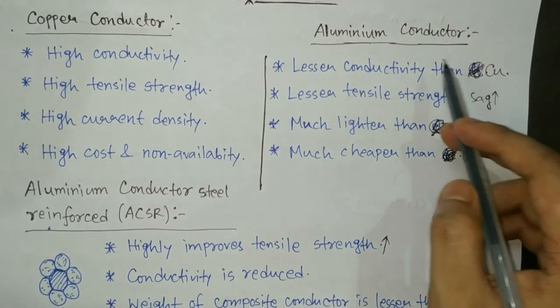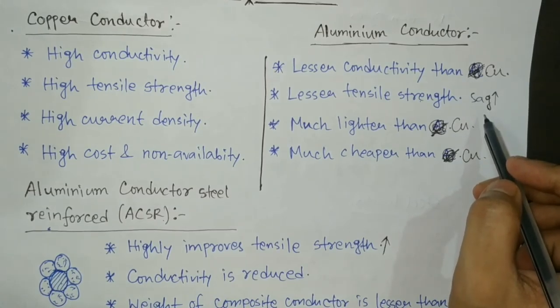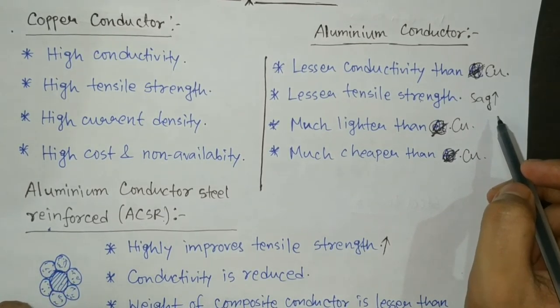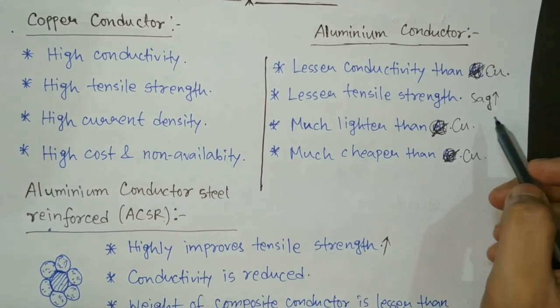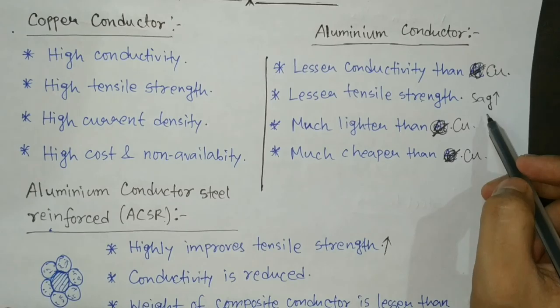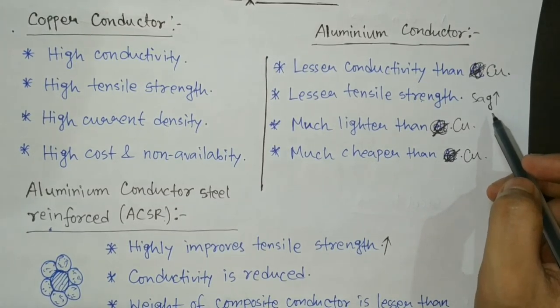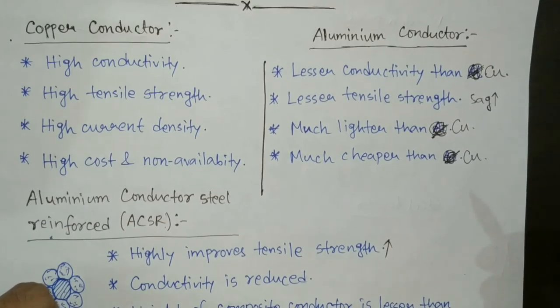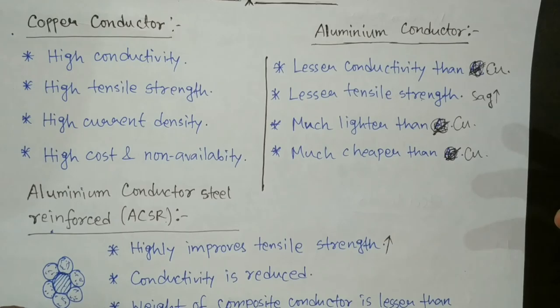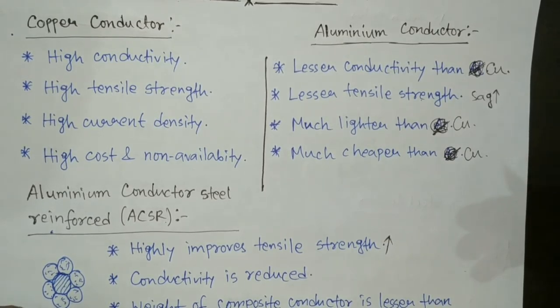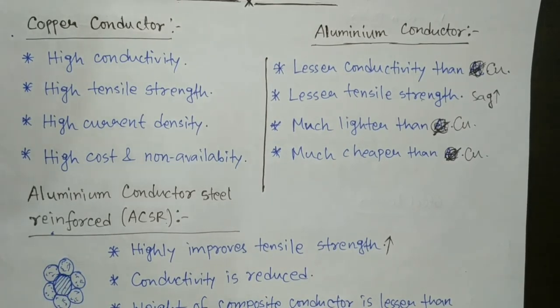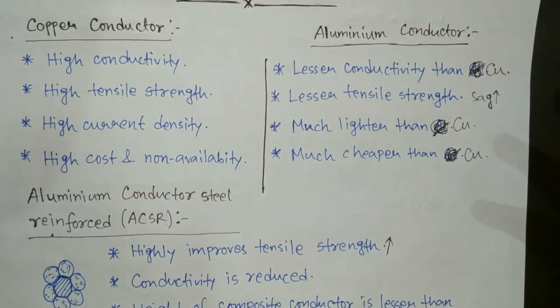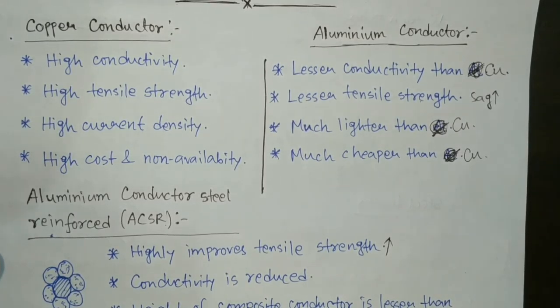In the case of an aluminium conductor, due to the high sag, the line span cannot be increased to a large distance, because a longer span increases sag further. But with ACSR, due to the improvement in tensile strength and reduced sag, you can now place the transmission towers at a longer span — at a longer interval. This means the number of towers also gets reduced, which results in a further reduction in cost.